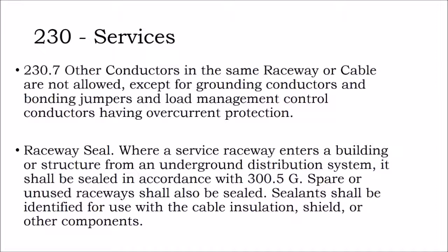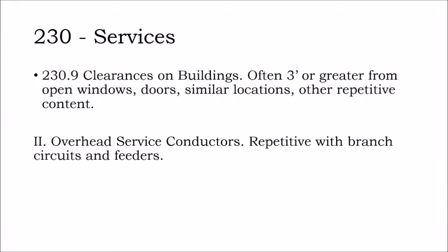Okay, so then we have other conductors in the same raceway or cable are not allowed except for grounding conductors, bonding jumpers, and load management control conductors with overcurrent protection. And then we get another raceway seal call out that says you have to seal your raceways. We've already seen those scenarios when we were talking about feeders, and they're the same for services, which are a specific type of feeder and therefore come after the feeder section. The requirements are pretty much the same, but feeders and services cannot share conductors with load devices. Same clearance requirements.